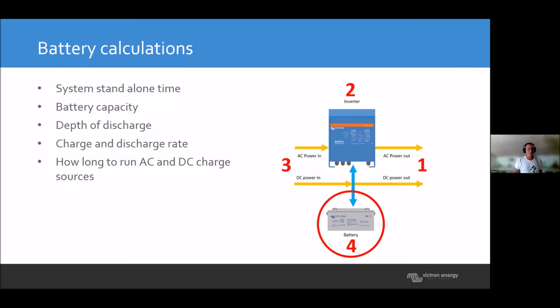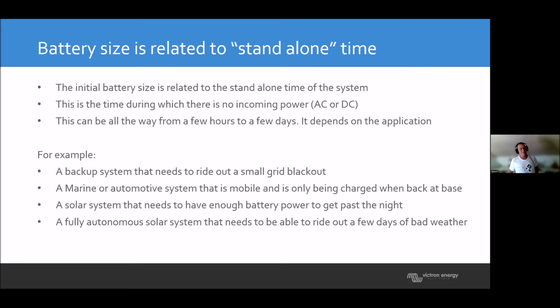Battery calculation is one of the most important things - calculating that the battery is the correct size. The battery size is calculated first to the standalone time, but also to the consumption from the system, because when you calculate the system in watts or kilowatts, you must also count it back to the battery, so you can see the battery can supply the amps when it's coming out, since we're sometimes talking about quite high amps from a battery.